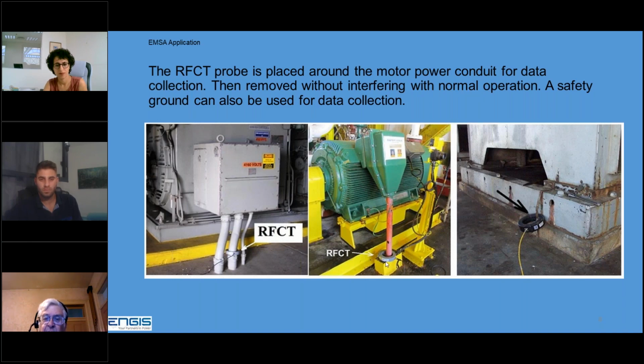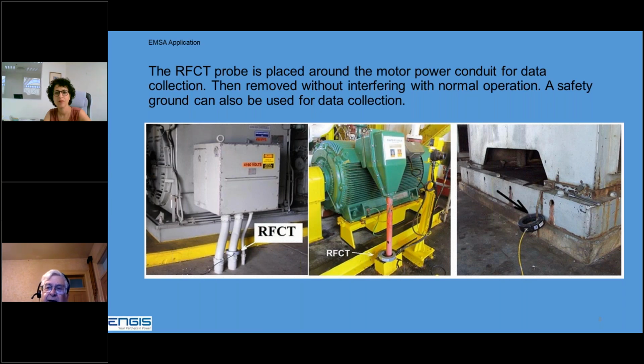For most motors with one power conduit, the RFCT is placed around that. If there are 2 conduits, we take the one on the right. If for some reason you can't get at the conduit, then we can put the RFCT on a safety ground to the frame of the motor. I've even used an oil line, a bearing drain line on large motors when neither one of those were available.